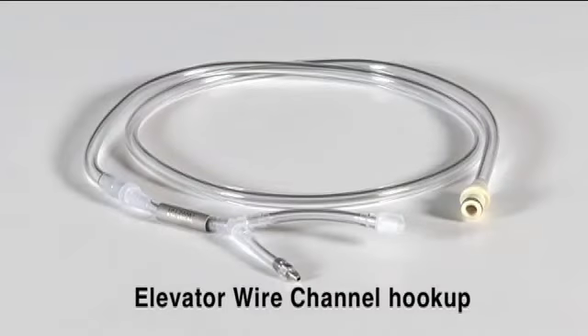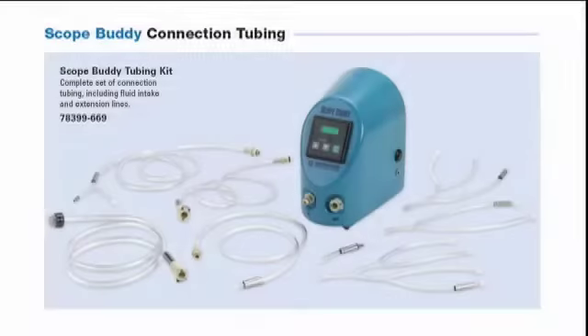Elevator wire channel hookup. This hookup snaps directly into the out port on the Scope Buddy unit and allows flushing of the elevator wire channel of a Fujinon duodenoscope or a Fujinon endoscope's forward water jet. For Olympus and Pentax endoscopes, the elevator wire channel and forward water jet can be flushed simultaneously with all other channels and does not need to be flushed independently using this elevator wire channel hookup. A more in-depth demonstration of the tubing connections and configurations will be presented later.